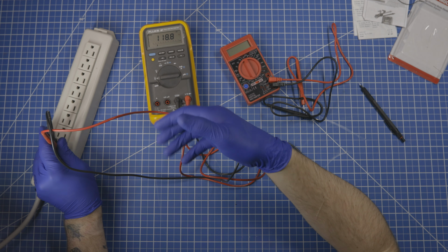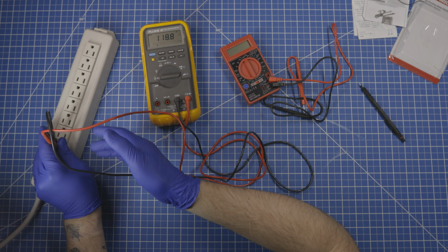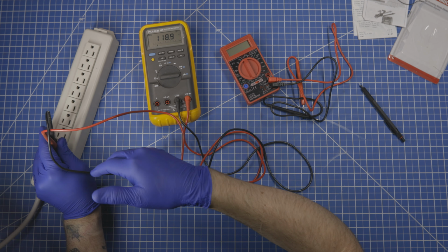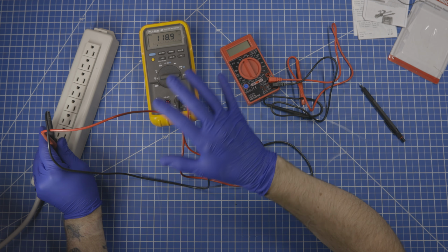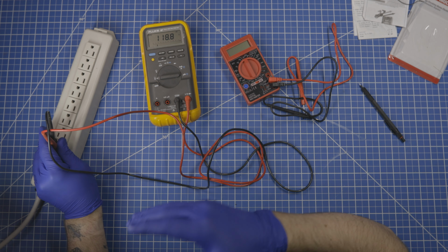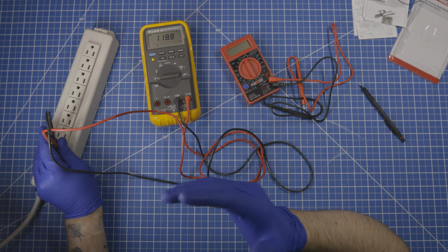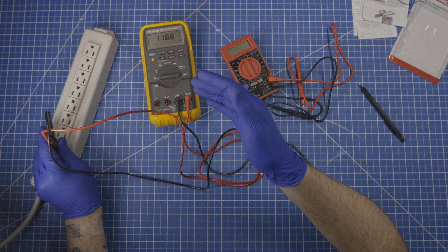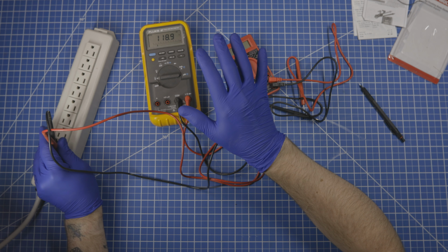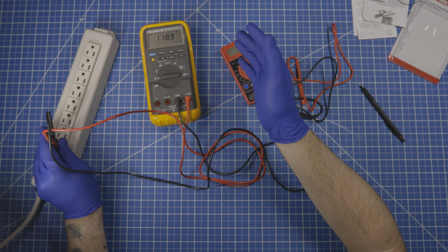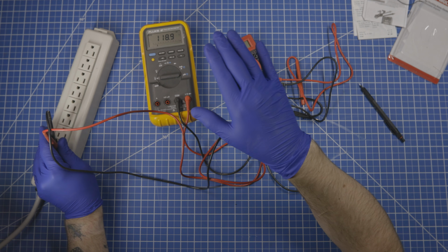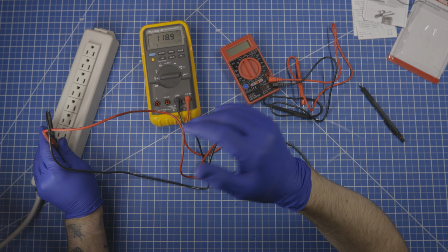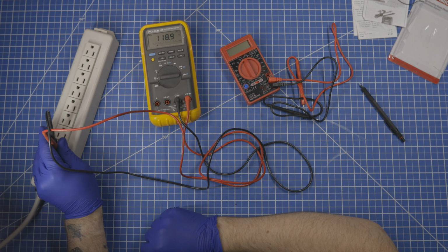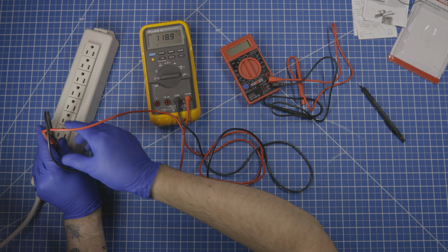The sign that something is amiss would be if this read 80 volts or 160 volts. That would be bad, way out of spec. But if it's anywhere between like 115 and 125, I'm satisfied that my outlet is working as appropriate. And it's steady as well, not constantly fluctuating by 10 volts or something like that.